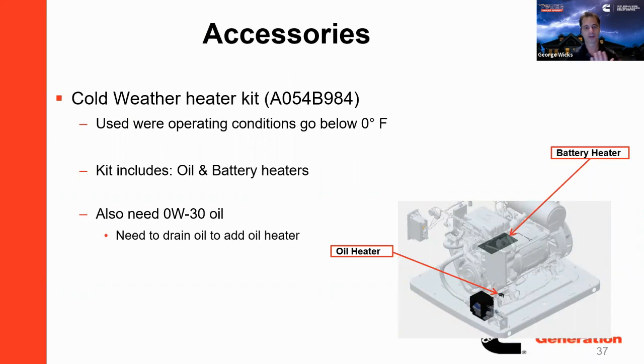The other option is cold weather heater kits. An additional oil-based heater and a battery heater is considered an extreme cold weather kit, so now we're talking about -20, -30 spec. We do have homeowners that want that. They go outside in the winter and feel 10-degree chill air, or 15 degrees here in Pennsylvania, New Jersey, and when it comes January, they think, ooh, that's cold for my generator. Yeah, it's cold for you, but for an engine made with metal and oil and air cooled, it's going to run and start with the standard heater. But we do have the extra accessories, and it could be argued, and I have, that it could extend the overall life expectancy of our generator by having an oil-based heater warming that engine block throughout its entire life expectancy and all those cold winter starts. So it's a nice feature to offer.